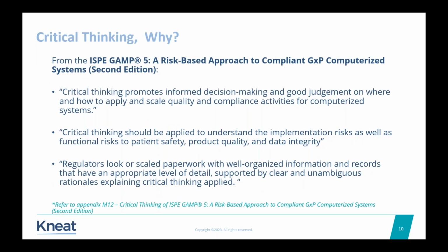So critical thinking, where did this critical thinking come out of? Okay, I'll just go through a few things here in terms of critical thinking. This is from ISPE GAMP 5, risk-based approach to compliant GxP computerized systems. Critical thinking promotes informed decision-making and good judgment on where and how to apply and scale quality and compliance activities for computerized systems. Point number 2, critical thinking should be applied to understand the implementation risks as well as functional risks to patient safety, product quality, and data integrity. And third point, regulators look for scaled paperwork with well-organized information and records that have an appropriate level of detail, supported by clear and unambiguous rationales explaining critical thinking applied.